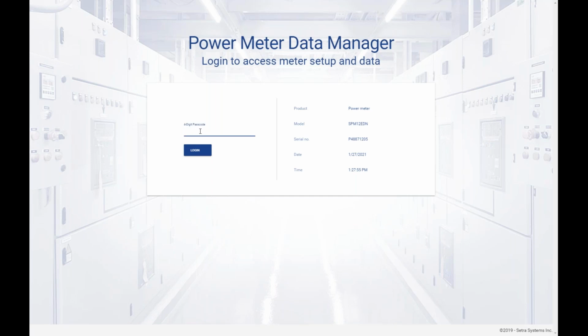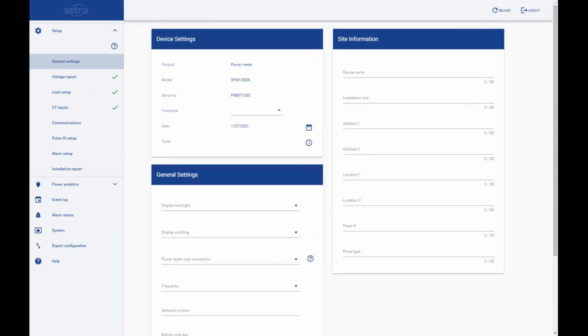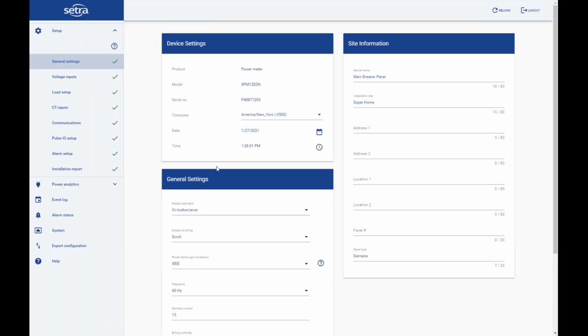I'm tied into the Power Meter Data Manager, which is the software located on the unit itself. So let me dial in here with my PIN code. From here, the web portal software is split into a sidebar for navigation. So you have setup, and then you have informational for different trending things that you can look at, event logs, alarm status below there.